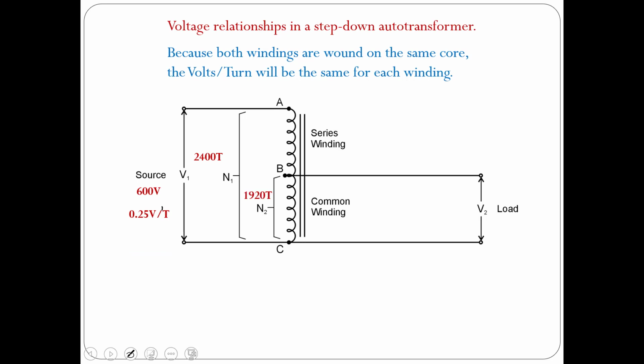Okay, the turns on the common winding, if we had 1,920 turns, so 1920 times 0.25 volts per turn. Okay, what would that give us? That'd give us 480 volts. So 1920 turns times a quarter volt for every turn gives us 480. And we could figure out the voltage of the series winding too if you wanted to. 480 plus 120 would be 600, so that'd be 120 volts on the series winding.